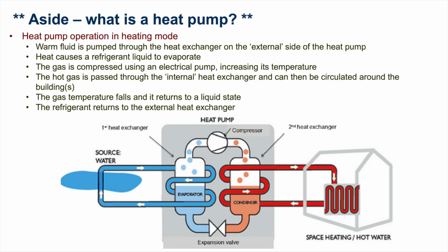We have our source, groundwater for example, coming out, and if we're using this for heating, we have a fluid with a very low boiling point, so just adding that bit of heat from the groundwater is enough to make it boil. We pass it through a compressor, not a pump — we compress it, and that's where the electricity supply comes in, compressing the gas, which raises its temperature. We then pass that high temperature through another heat exchanger into the fluid that heats the building. That cools the gas, which recondenses and passes back through the heat pump to be boiled again, and so on.